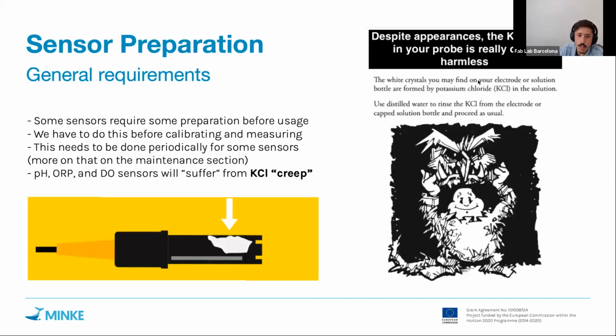So, general considerations. You will see that a lot of the sensors have something that we call KCl creep, or potassium chloride creep, which is basically a small crystal deposit on the probe itself, due to a consequence of how we store the sensor and the chemical composition of the sensor. So there's no problem with it. You can just clean the sensor with tap water or distilled water, and we are ready to go. This has been happening forever in all the different sensors, and you will notably see this on pH, electric conductivity, dissolved oxygen, and ORP sensors mostly.